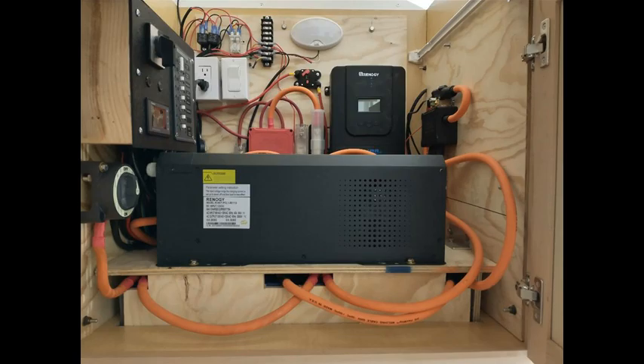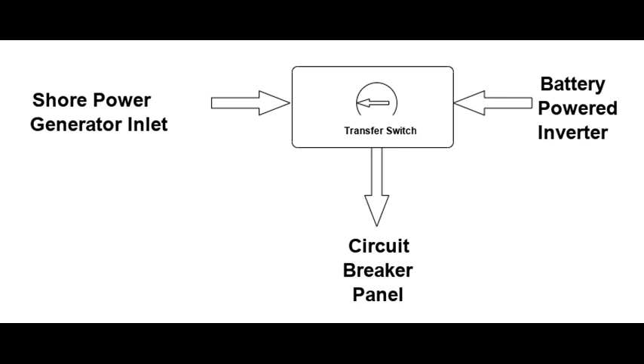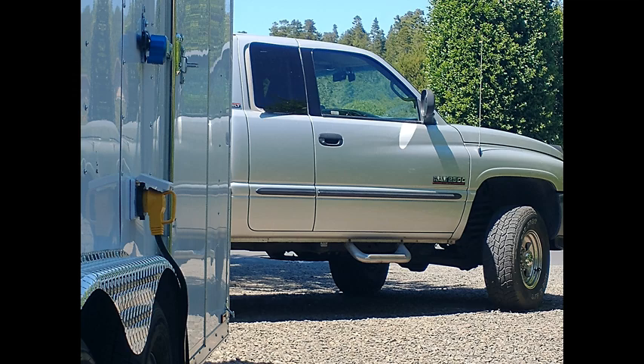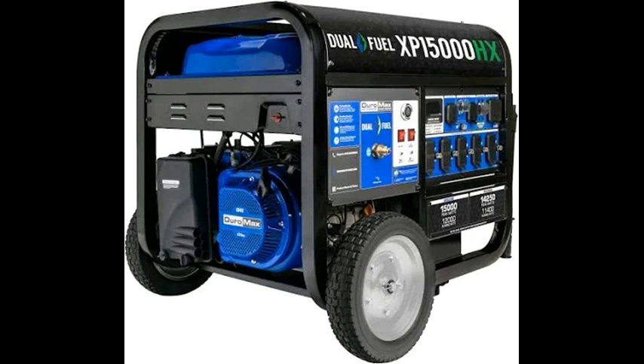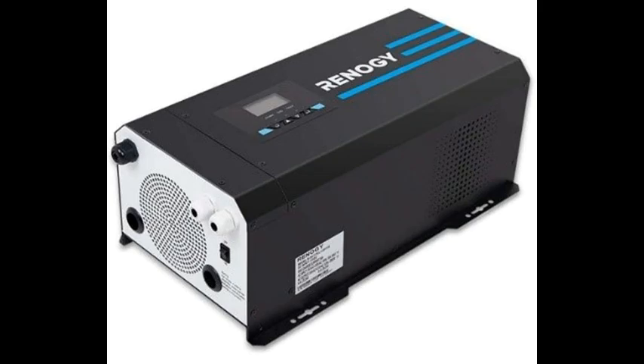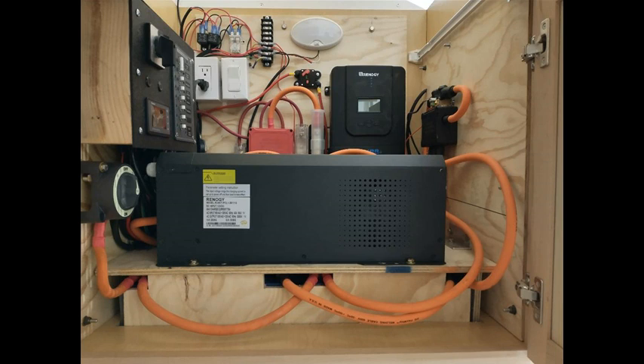Step 8, the transfer switch. This is a very important part of the big picture and protects components and people by making sure electrical energy is where it is supposed to be. The transfer switch ensures that power to your AC circuit panel is from only one source at a time, and guarantees that there's no source able to backfeed to another. Also remember that power from all sources needs to be switched, whether it's from the battery pack or any other source. That means the solar arrays need to be switched, the battery charger, and all of the AC sources.